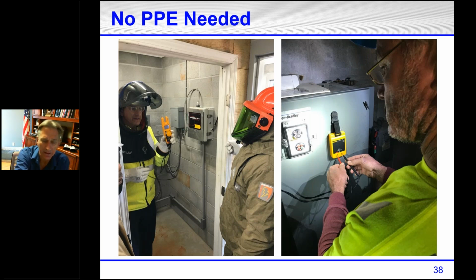The guy on the right in the left picture is suited up because I had them go into this equipment doing voltage testing and current measuring, knowing what all to wear. The gentleman in the picture on the right, not wearing any PPE, is on the outside of the equipment, first testing the meter, then testing for the absence of voltage, then testing the meter again. At that point, he can open the equipment up without wearing shock or arc-rated PPE.